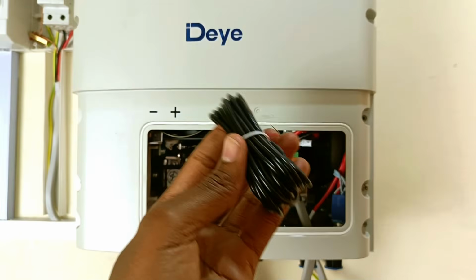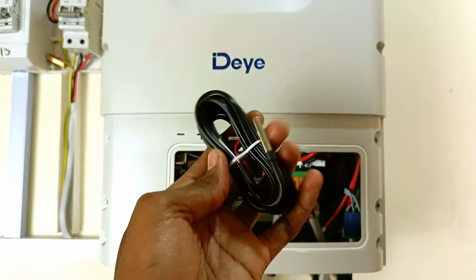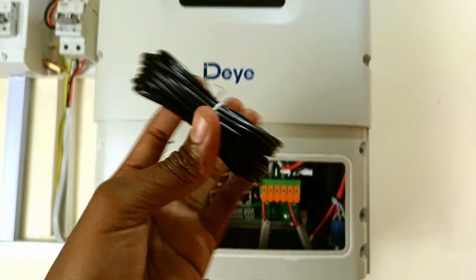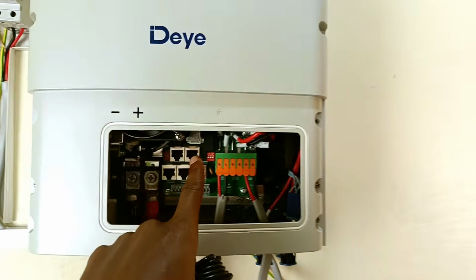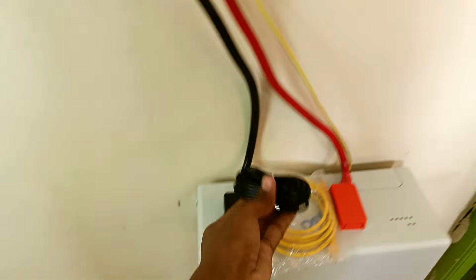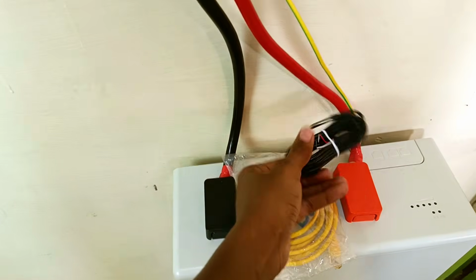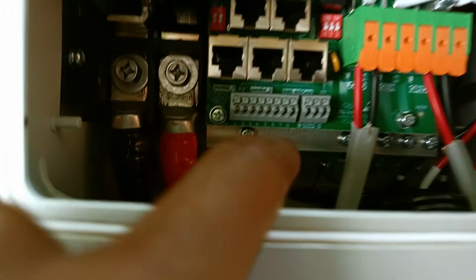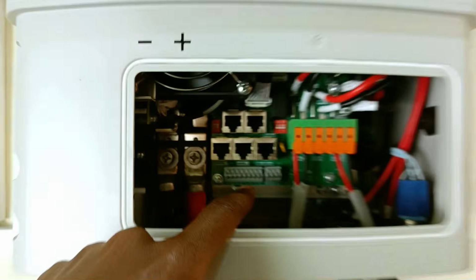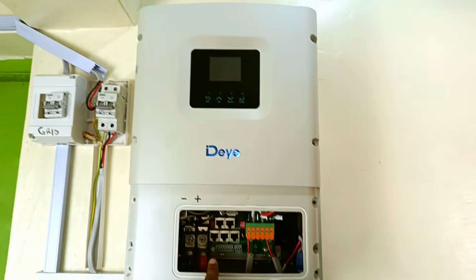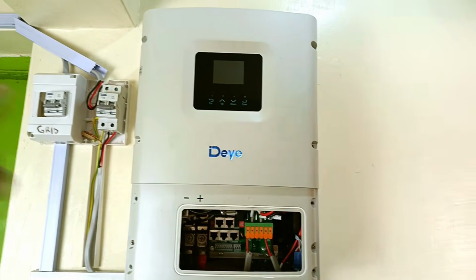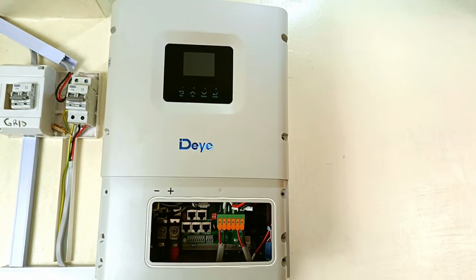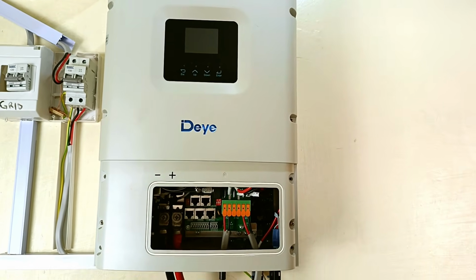Number 5 and 6 are for connecting a battery temperature sensor, and that's if you are using a lead acid battery. But I don't need that since I will install an Ethernet cable from the inverter to the battery. That eliminates me using the battery temperature sensor. And finally, number 7 and 8 are for connecting a current transformer coil. This inverter didn't come with that current transformer coil, but it's normally used to track the consumption from your grid.